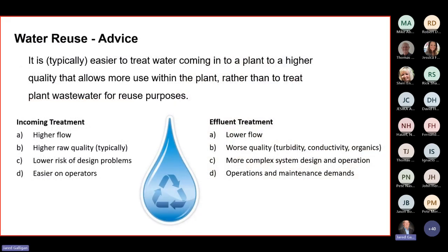From my years of experience doing water treatment, water reuse, and wastewater treatment projects, some general advice: it's typically easier to treat water coming into a plant to a higher quality that lets you use it more, rather than treat the wastewater coming out with the intent to reuse it. What I mean is, say a facility has a cooling tower, a large water user in most facilities. It's often easier to treat the incoming groundwater or city water to a very high quality that allows the cooling tower to use that water more efficiently, or more times, before you discharge it, rather than take the effluent coming out of the cooling tower and treat it for reuse back into the tower or some other user.